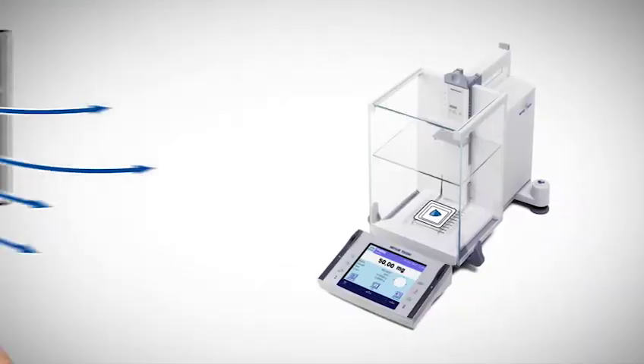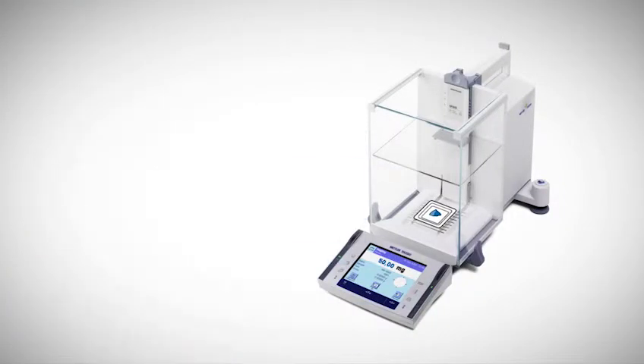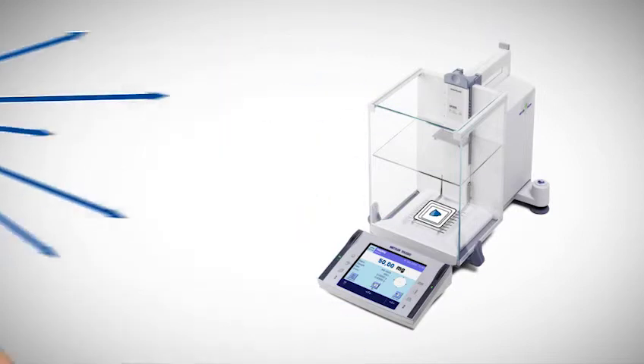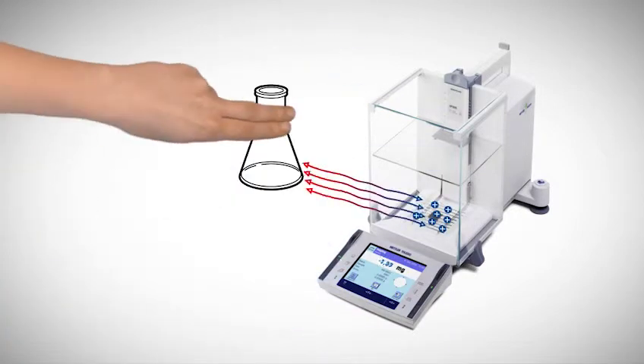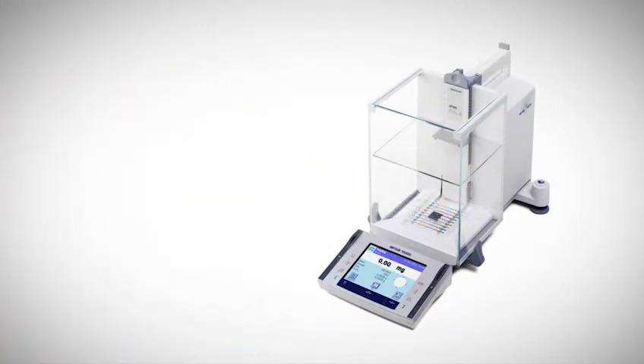USP 1251 provides practical recommendations for the qualification and operation of balances. Among others, it describes several environmental factors that can influence the performance of a balance. For example, air currents, temperature variations, vibrations, electrostatics, and many more.